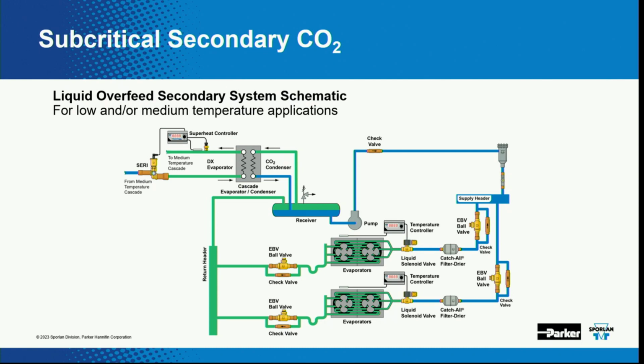Coming out of the coil, I've shown the ball valve with the check valve in parallel. I didn't show the Sporlan integral valve, but nevertheless, that's there. Return suction header goes back to what's being called a receiver. It's a vessel. Yeah, thank you. That's the right word. It's a vessel. It's not really a receiver in the traditional sense, but from that vessel, again, we're just going to pull the liquid off. We don't want to cavitate in the pump, and then we circle it right back around again, and then the CO2 is being cycled through that heat exchanger to bring that temperature down.